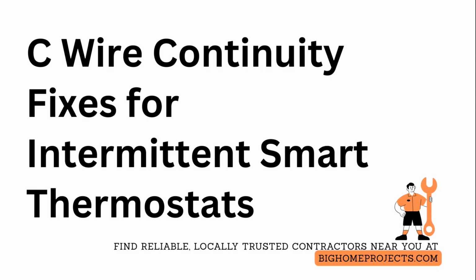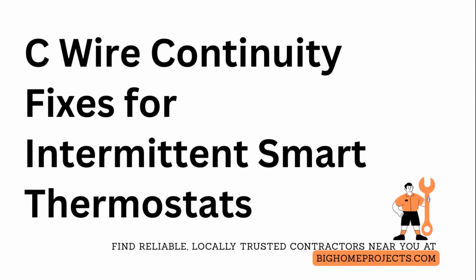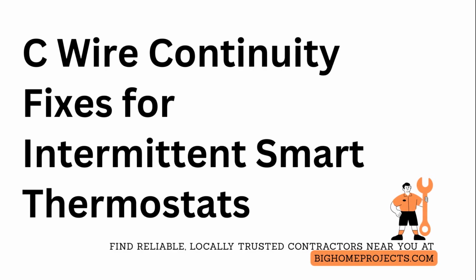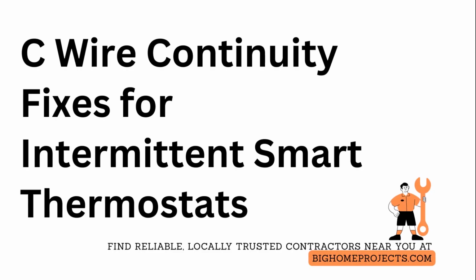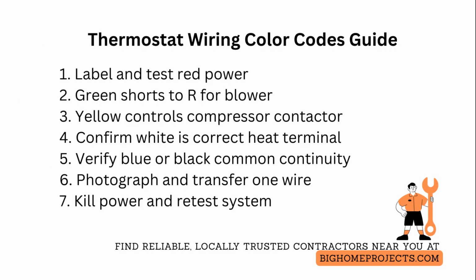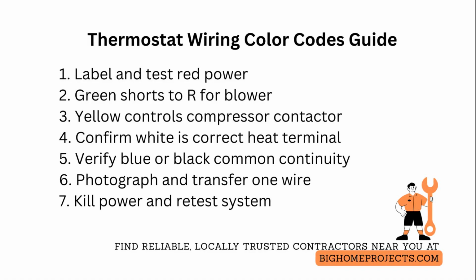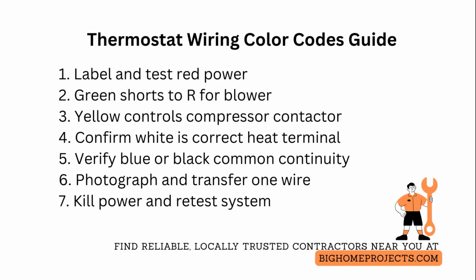Clear, color-coded thermostat wiring keeps your heating and cooling system safe and dependable, so know exactly what each wire does before you touch anything. Red is the 24-volt power lead from the transformer. Label it R and check with a multimeter set to AC volts before disconnecting.